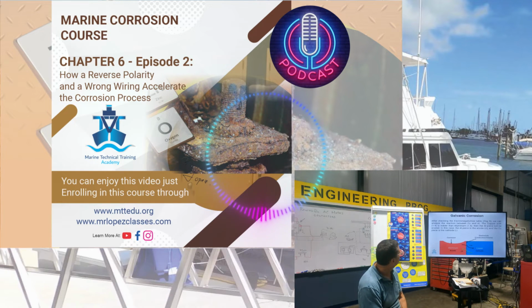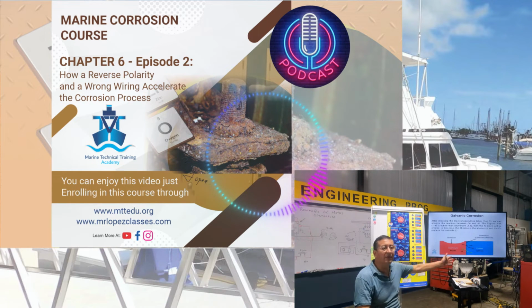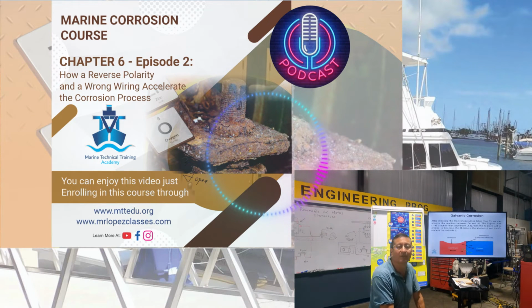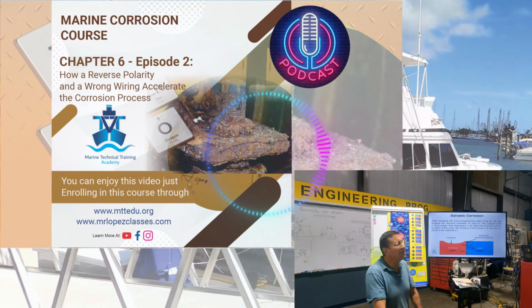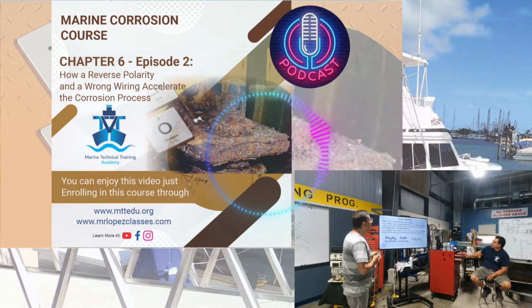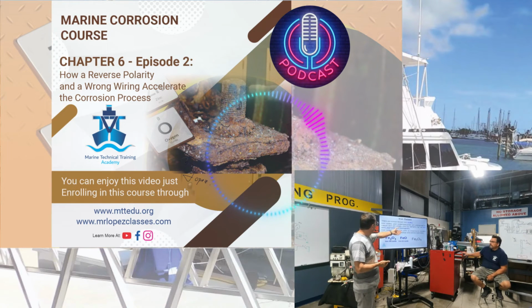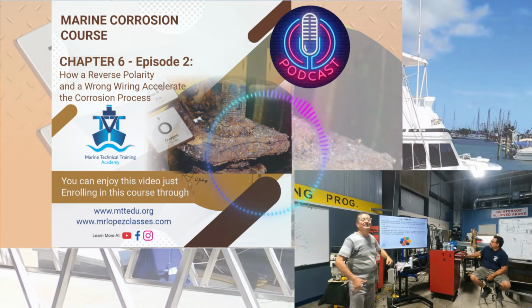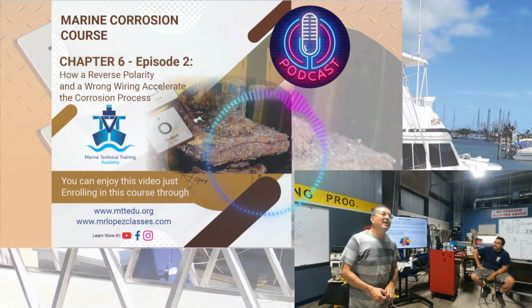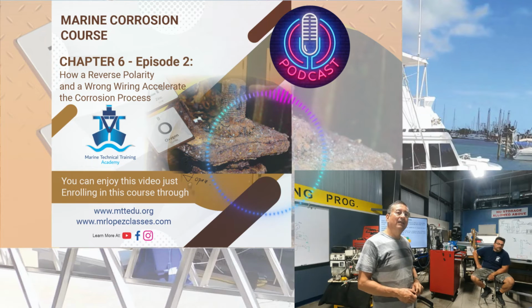The ground in this particular case is here. That's the ground bus bar. The ground bus bar goes directly through the transformer and is interrupted in order to insert the galvanic isolator and continue over there. When you insert the galvanic isolator, remember that episode related with the galvanic isolator: the capacity of the galvanic isolator in amps should be exactly the same as the capacity of the main breaker on the AC panel.